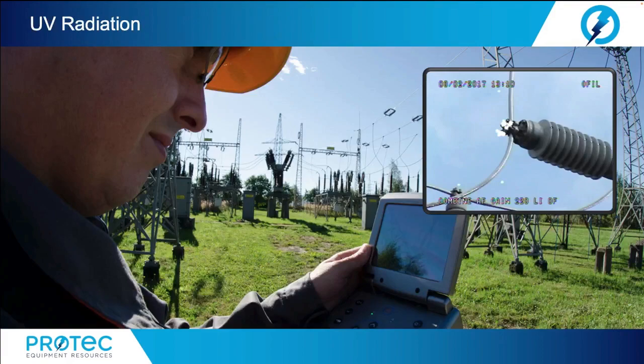All right, now let's talk about UV radiation. Corona discharges generate electromagnetic radiation in the range of 200 to 405 nanometers. Solar radiation also contains, in addition to visible light, both infrared and ultraviolet radiation. Using an appropriate filter, with wavelength ranges from 240 to 280 nanometers, we can suppress UV radiation generated by the sun, so the camera may operate well in daylight without interference.